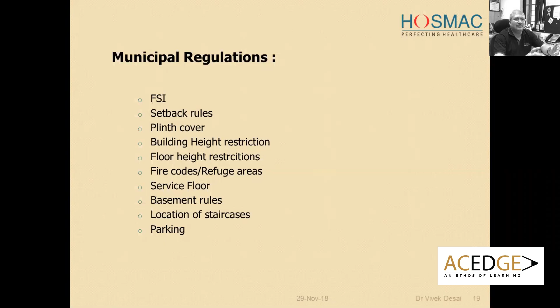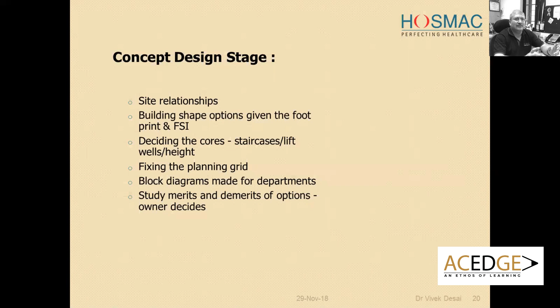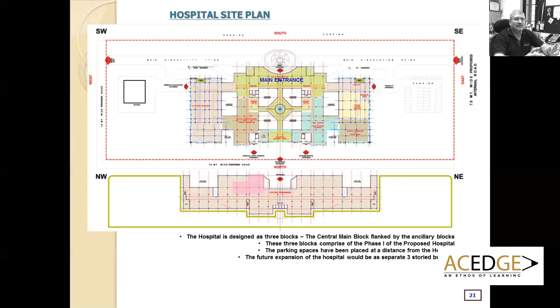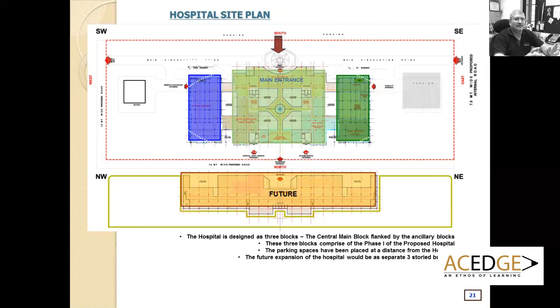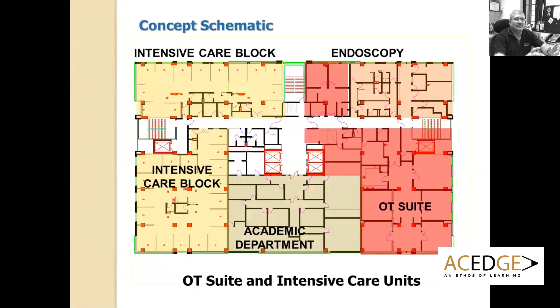Location has to be as per the fire norms, so that is something that we can't do anything about. One thing that is very sacrosanct to us is the planning grid, the column grid. Let me skip this. This is important for us in terms of the grid. All those red squarish things you see are the column grids, and for us, if you see the operation theatre that you just went by, this operation theatre suite has to be beam free. There should be no column.